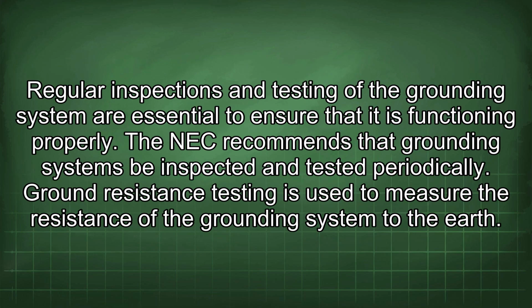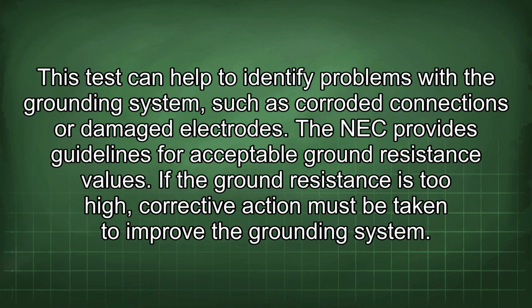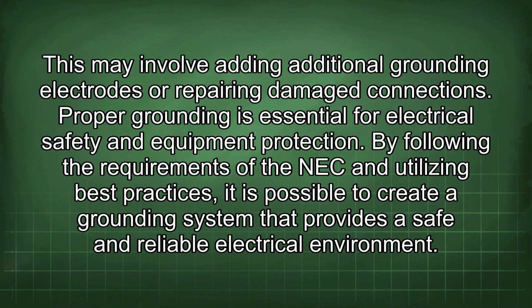Regular inspections and testing of the grounding system are essential to ensure that it is functioning properly. The NEC recommends that grounding systems be inspected and tested periodically. Ground resistance testing is used to measure the resistance of the grounding system to the earth. This test can help to identify problems with the grounding system, such as corroded connections or damaged electrodes. The NEC provides guidelines for acceptable ground resistance values. If the ground resistance is too high, corrective action must be taken to improve the grounding system. This may involve adding additional grounding electrodes or repairing damaged connections.